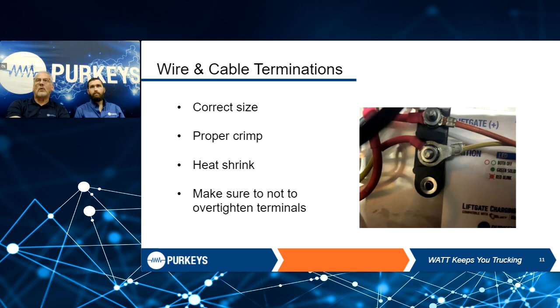When I start looking at my wire ends, we got to make sure they're the correct size, meaning the eyelet is the right size, not too big. As you look at this picture, you can see the eyelet on that white or yellow wire is quite a bit larger than the stud, and also larger than the wire itself. It's probably made for about a 10 gauge wire, and you're only looking at a 16 to 18 gauge there.